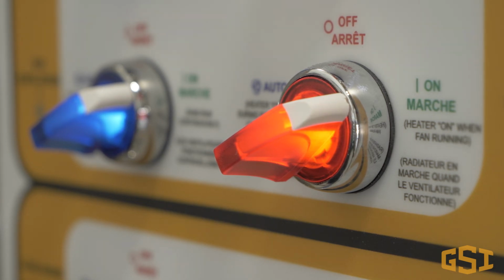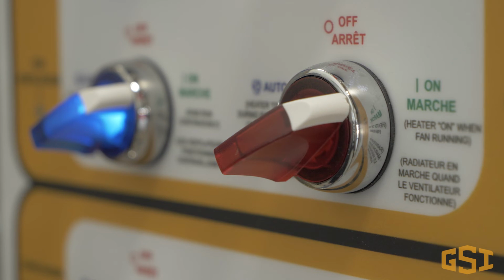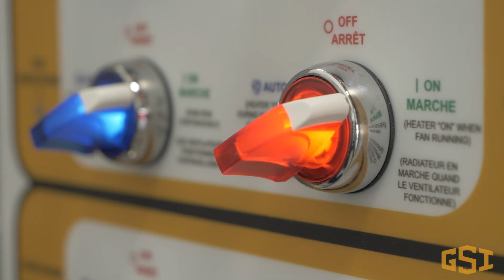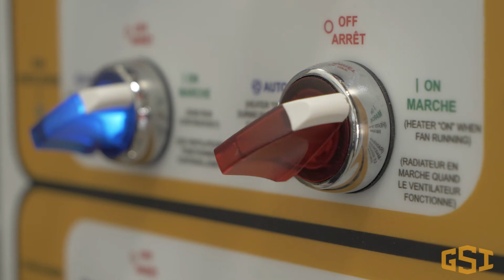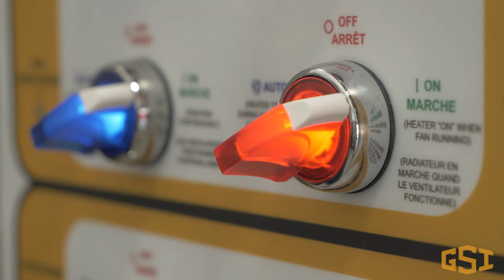If at any time the flame does not touch the flame probe, the connection is broken, which results in a loss of flame shutdown. You can monitor the physical connection between the flame and the flame probe with the light on the burner switch. It will go out when that physical connection is broken. Use the burner light as a service tool for when the flame and flame probe are touching. The light should always be on when the burner is in operation.